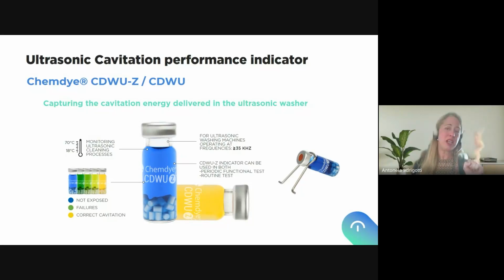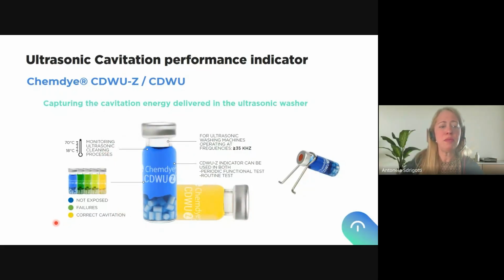So what is the aim of this indicator? What will happen if we put this indicator inside the machine once I have the solution, the detergent, and the right temperature? And we start after the degasification, we make a short cycle. The vibration of the cylinders in this case will trigger a chemical reaction that will start a color change from this blue through different shades of green until arriving to the correct cavitation energy, which is this yellow, okay?